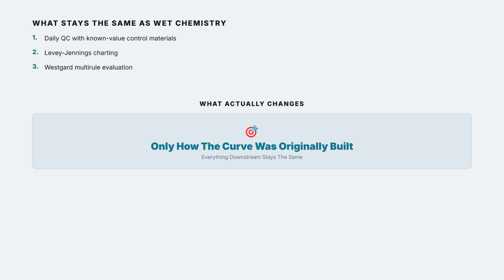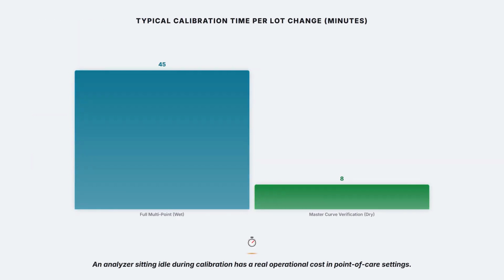This master curve model carries a real practical upside worth naming directly. Dramatically less hands-on calibration time per lot change compared to running a full multi-point curve, which matters enormously in point-of-care and high-throughput settings where an analyzer sitting idle during calibration has a real operational cost.